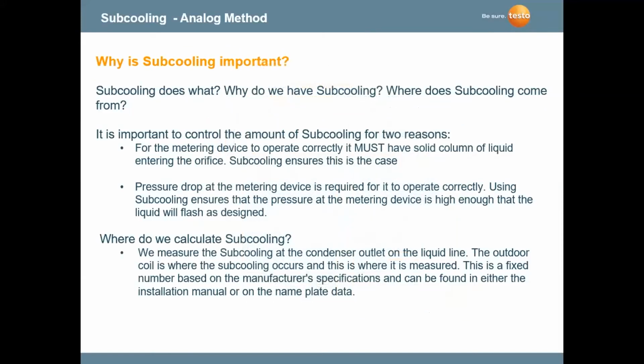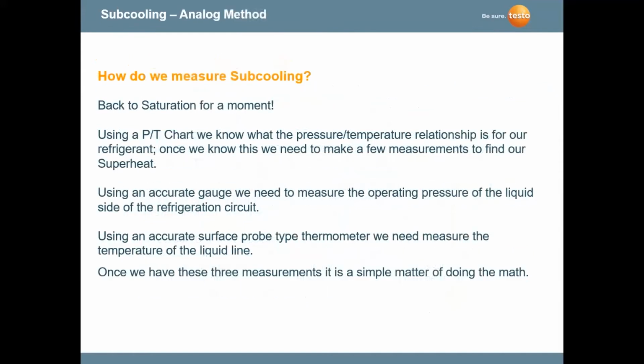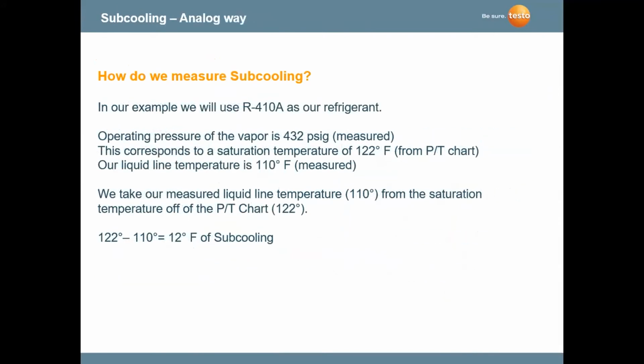Subcooling, again, we must have a solid column of liquid entering the orifice. And again, we're using a PT chart. We're on the high side of the system. We're using a high pressure gauge and an accurate surface thermometer, and we're looking at 432 PSIG, which is measured. We take that, look at a PT chart that corresponds to 122 degrees Fahrenheit, and we look at our liquid line temperature, taking a measurement of that at 110, and we subtract the line temperature from the saturation temperature, which is 122 minus 110 to get 12 degrees Fahrenheit.